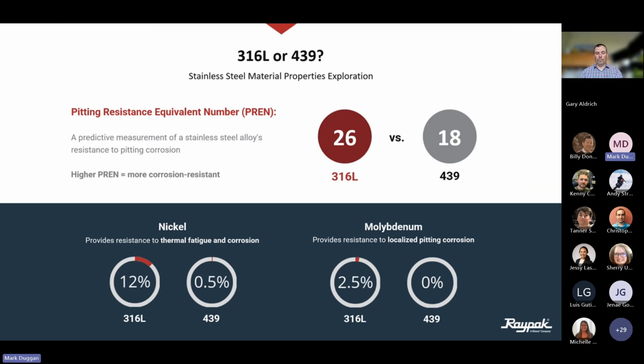So why do we use 316L stainless steel? A lot of manufacturers use that 439. It's a cheaper stainless steel. It works, but the reason we use that 316L is because it's got a higher pitting resistance equivalent number. That pitting resistance equivalent number, or PREN for short, is a predictive measurement of the stainless steel alloy's resistance to pitting corrosion. So the higher the PREN number, the more corrosion resistant it is. So that 316L has a 26 PREN number, whereas 439 only has an 18 PREN number.